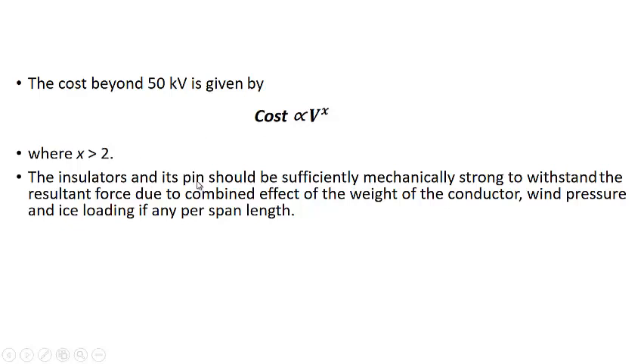The insulators and the pins should be sufficiently mechanically strong to withstand the resultant force due to the combined effect of the weight of the conductor, wind pressure, and ice loading, if any, per span length. We know that there is tension in the conductor, and finally this tension will appear on this insulator. The insulator and pin configuration should be sufficiently mechanically strong to withstand this resultant force.